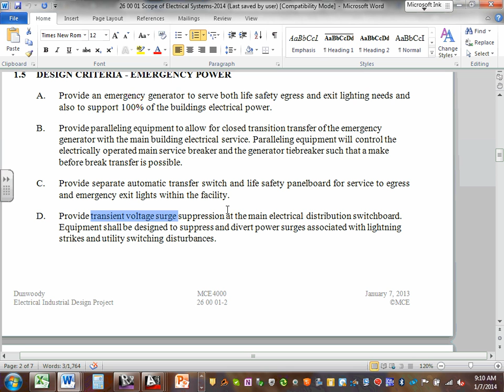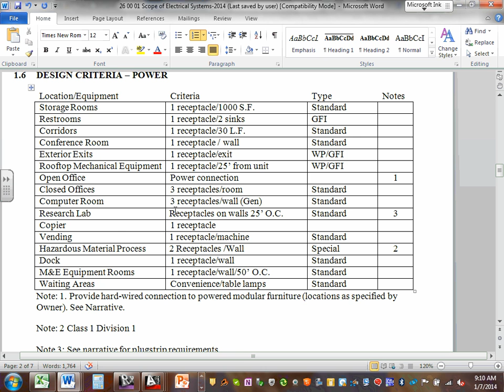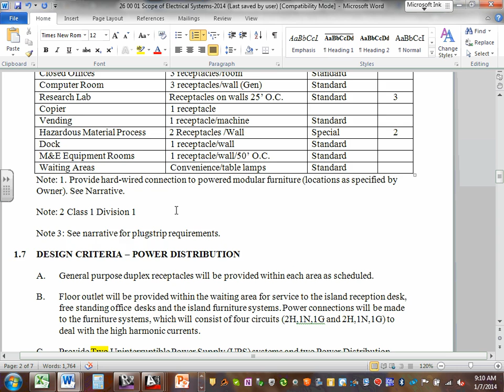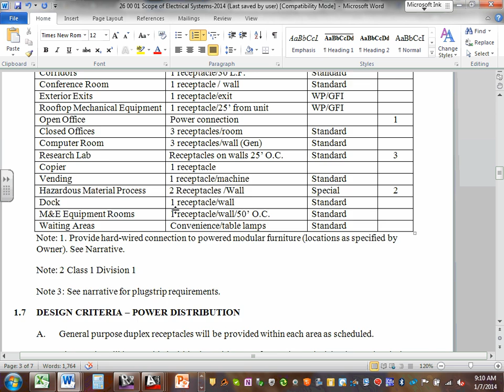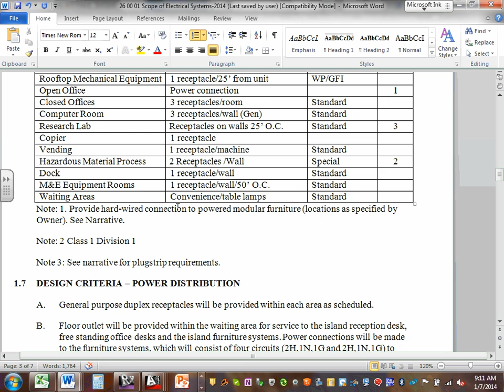We'll be having some surge protection devices. I should update that. They don't call it transient voltage surge suppression, TVSS, anymore. It's SPD now, surge protection device. Just industry jargon. Design criteria for power, we kind of talk about where the owner thinks that they need power. Most of that's pretty self-explanatory. Power distribution, there's going to be some floor boxes in certain areas. There's going to be furniture systems. This was one thing we tweaked from last year, that we're going to be doing 4 circuits to the furniture systems. This is sometimes referred to as 2+2. 2 hots, 1 neutral, and 1 ground, and then 2 hots, 1 neutral, and 1 ground. Both of those will be going to the spine.